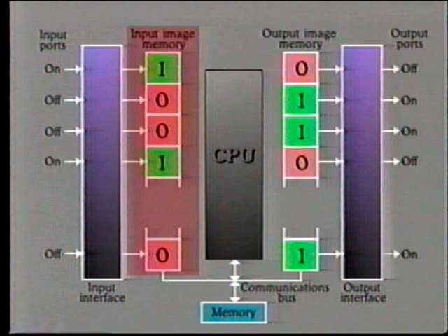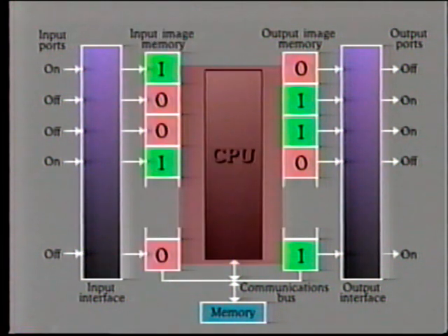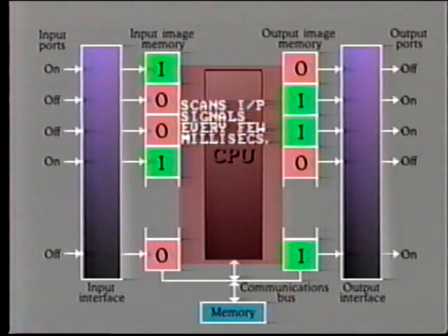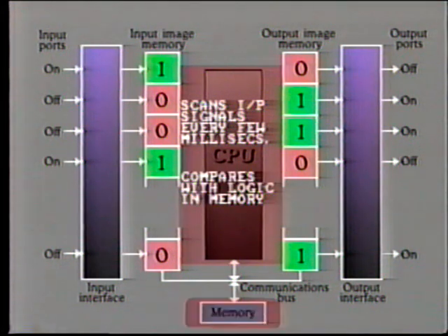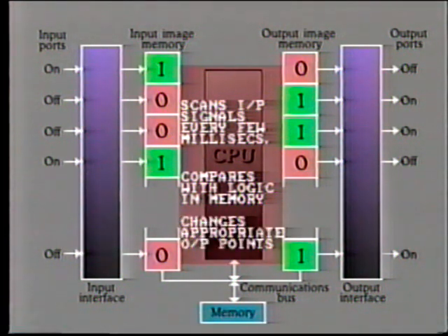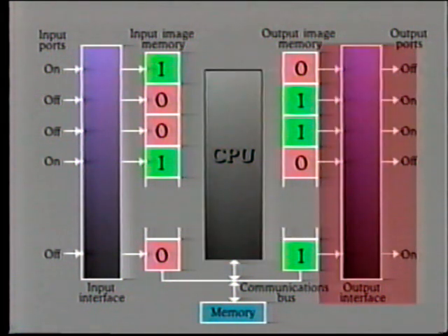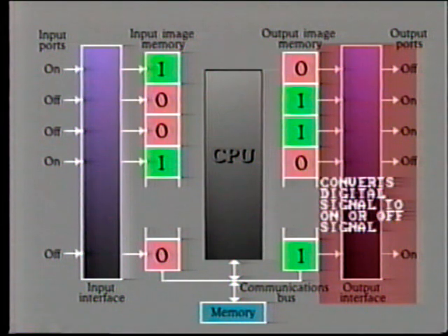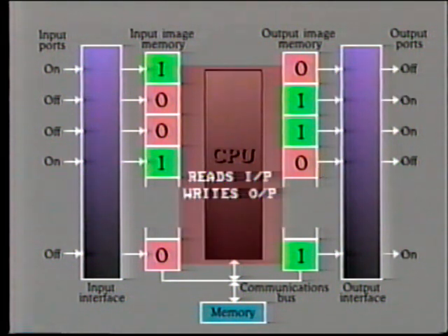By scanning this input image memory, the CPU can enter this information into the register for processing. The CPU carries out this scan every few milliseconds and compares the indicated status with the logic which is programmed into the memory. If the result indicates that some action is required, it will change the appropriate output points on the output image memory. This output digital signal is then converted by the output interface into an on or off power signal. The CPU is said to read the input signals and write the output signal.